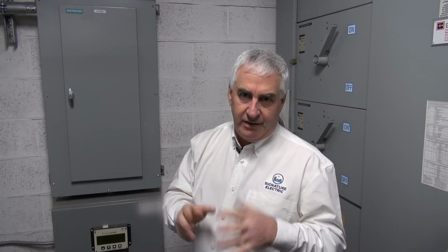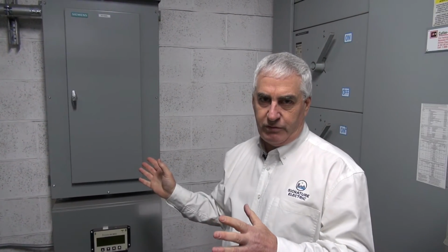There is a limit. This is an issue that we have to look at in terms of how far we can go. There's something called voltage drop, and it affects the size of the wire, and at about a couple of 100 feet or a bit more, maybe 250, that's about as far as we can go. So we have to think about whether this panel is sort of central in the garage, or if it's a big garage, we might need more than one panel, one place, another to service it.